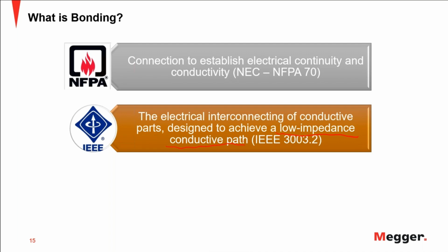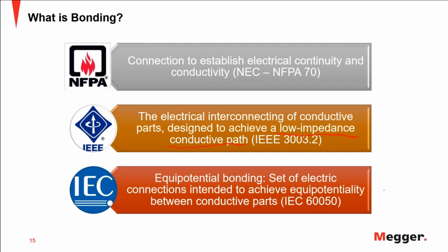You're talking about an actual low resistance. IEC is probably not a common standard for us, but especially in photovoltaic systems, they are ahead of the IEEE standards, and so typically those are used as reference here in the US as well. And for the IEC standard, equipotential bonding is the set of electric connections intended to achieve equipotentiality between conductive parts, and equipotentiality is the key word here.